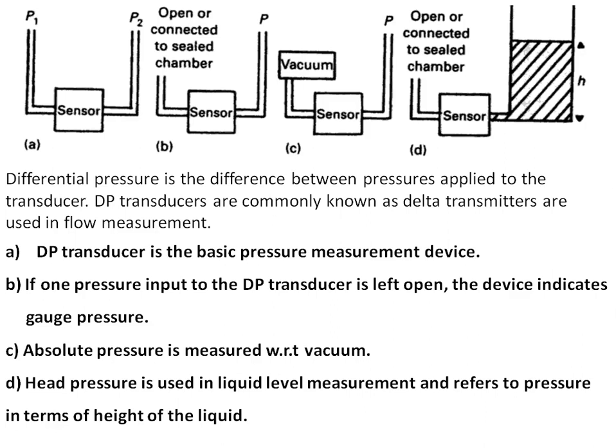In figure B, if one pressure input to the DP transducer is left open, the device indicates gauge pressure, generally with reference to atmospheric pressure. Figure C represents absolute pressure, which is measured with respect to vacuum — ideally zero pressure.